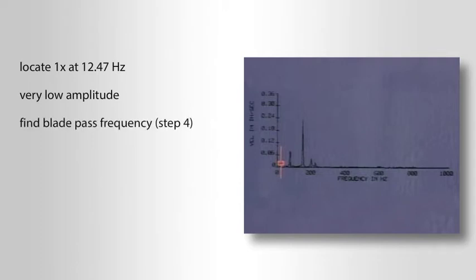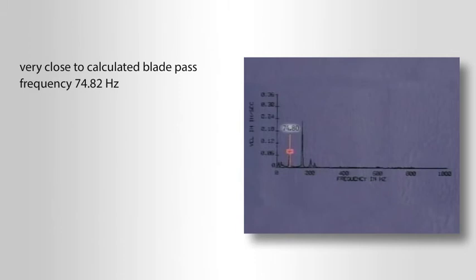We'll find the blade pass frequency in step four by placing the cursor on the first distinct peak to the right of the one-times. We find a frequency of 74.80 hertz, which is very close to our calculated blade pass frequency of 74.82 hertz, and we know we have identified the blade pass.